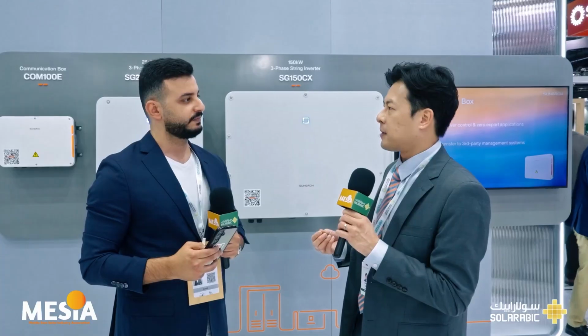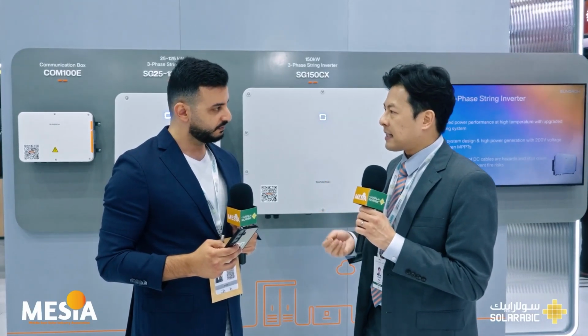Secondly, what we offer here is zero voltage starting capability for black start. Conventionally, when starting the microgrid or the system, the key challenge is the inrush current. With the zero start technology we offer at Sungrow, we ramp up the voltage from zero, increasing it slowly and gradually. In this case, we can eliminate the magnetizing saturation of the system, which provides a very stable increment of the voltage during the ramping up stage, right? In this case, we can remove the challenge of the magnetizing inrush problem.